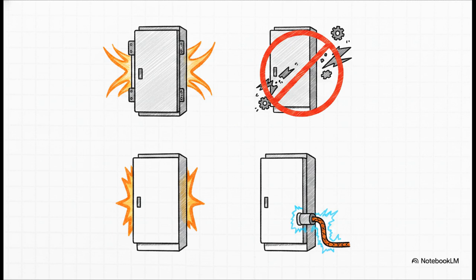This is governed by the IEC 60298 standard. It's basically a strict rule of 4 survival checklist that the hardware has to pass. First off, those doors, they absolutely must stay closed under the massive pressure of the blast. Second, absolutely zero hazardous parts can eject into the room where an engineer might be standing. Third, the enclosure itself cannot get pierced. Even the little visual indicators aren't allowed to burn through. And finally, every single earthing connection has to keep working, staying perfectly intact right through the middle of the fault.